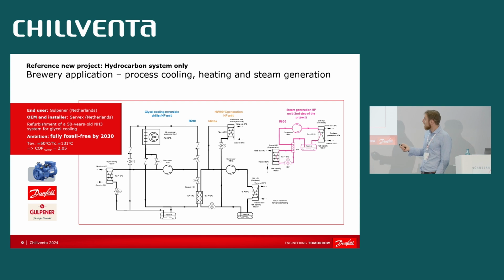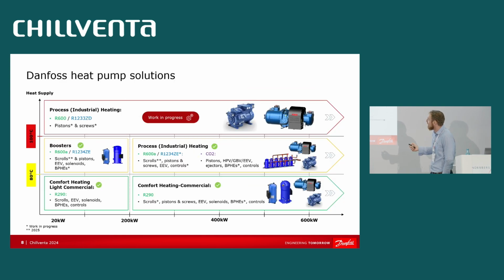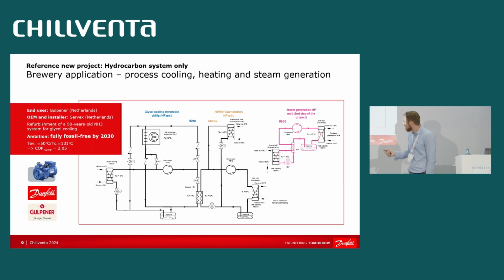Heating. That was a bit fast. So, heating. First stage, generating 90 degrees hot water with isobutane. Source of 40 degrees centigrade, either waste heat from the cooling system, or there is also the water tank with waste heat from processes. So we switch between sources upon availability. And then the third stage is the most interesting one.